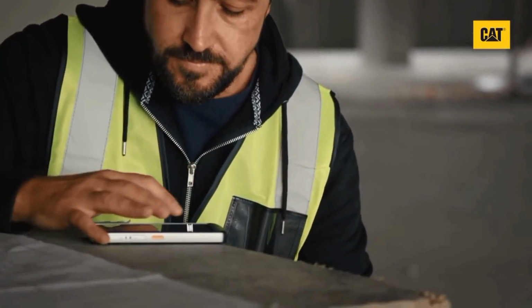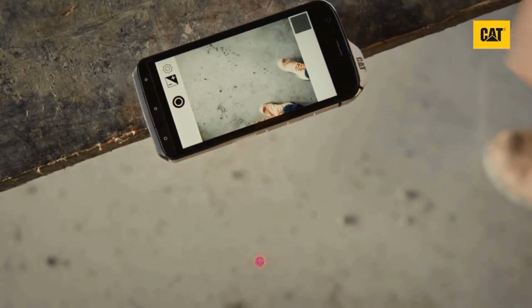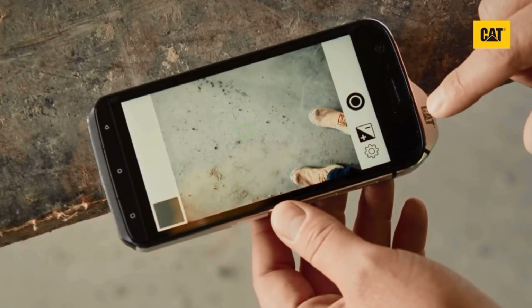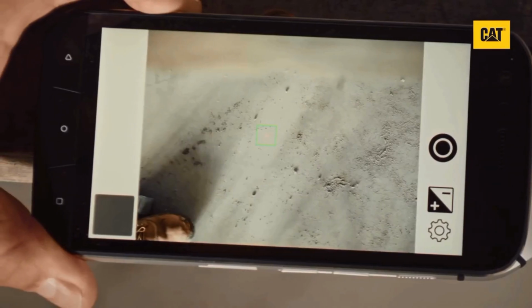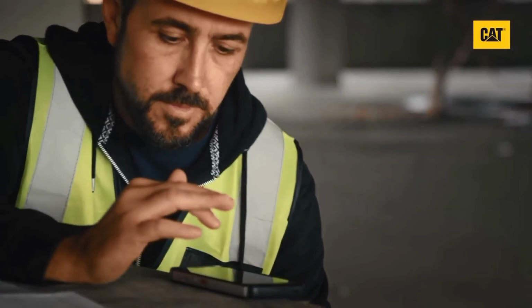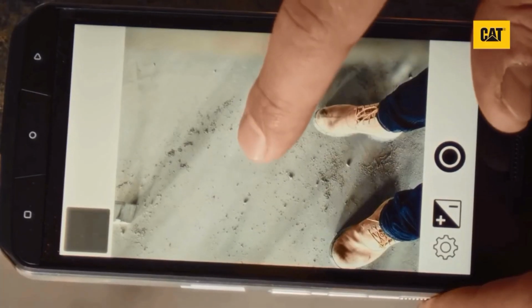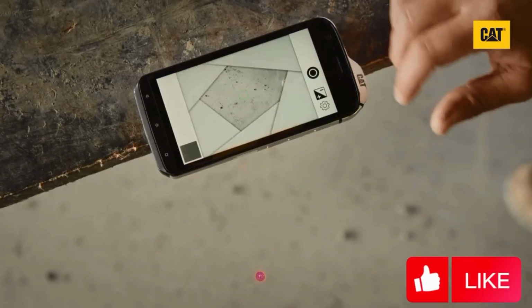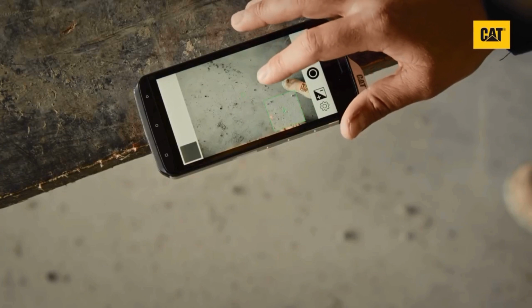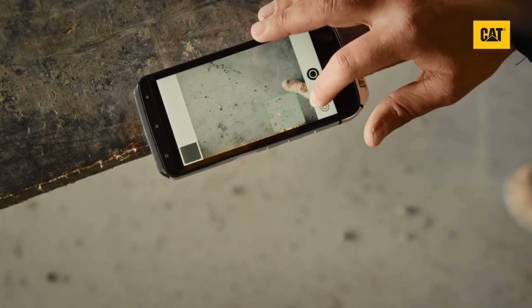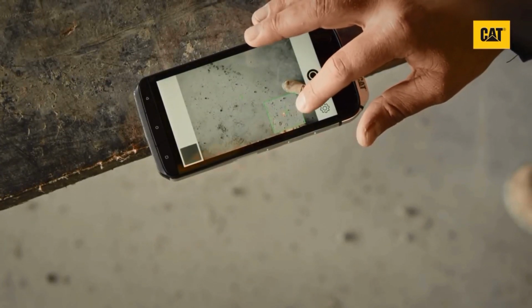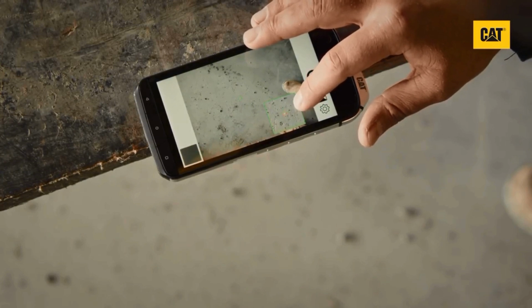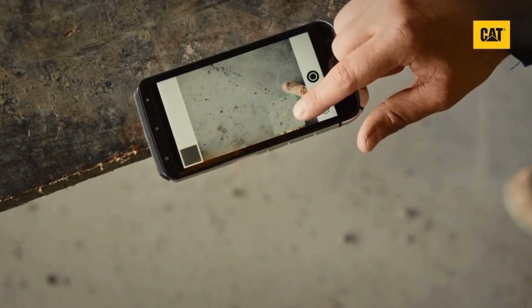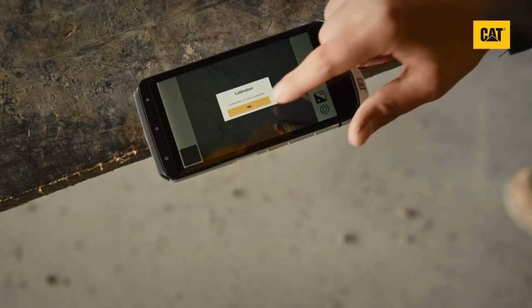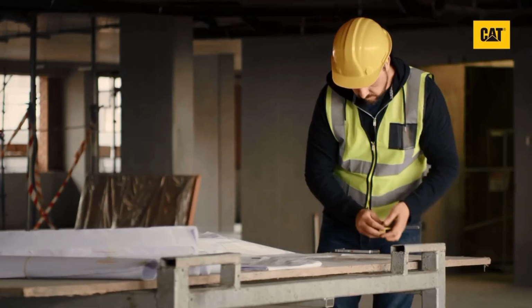app. On the next screen, the camera will attempt to automatically detect the red laser dot on the floor. A small green box should appear around the laser dot on the screen, indicating that it has been found. If the app struggles to find the dot, simply tap on the laser dot to manually identify. Next, tap the capture button. A magnified view of the laser dot will appear, with a crosshair in the center. Ensure the dot is in the middle of this crosshair by dragging the image as required, and press the capture button again to confirm. Calibration is now complete.